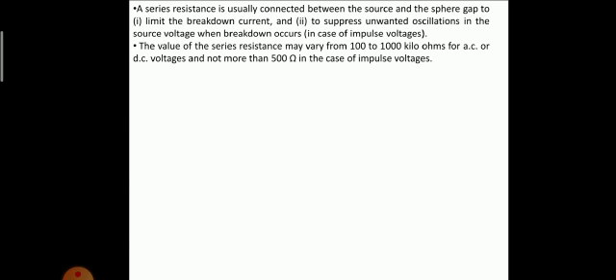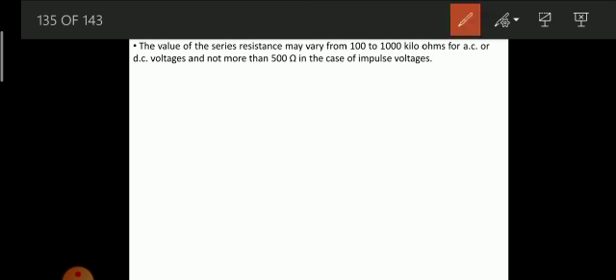Now the value of the series resistance which we will be incorporating can vary from 100 to 1000 kilo ohms for AC or DC voltages, and if you want to measure impulse voltage, it would go up to 500 ohms. This is what I said: there is a series resistance usually connected between the source and the sphere gap. The work of the series resistance is to limit the breakdown current and to suppress unwanted oscillations. The value of resistance can go from 100 to 1000 kilo ohms, or to 500 ohms.